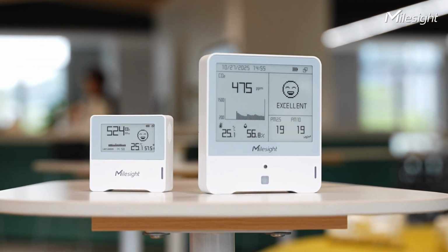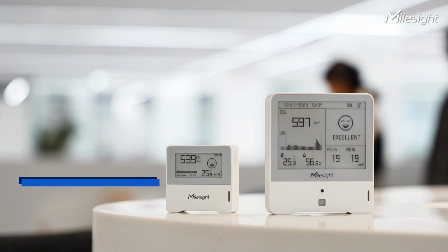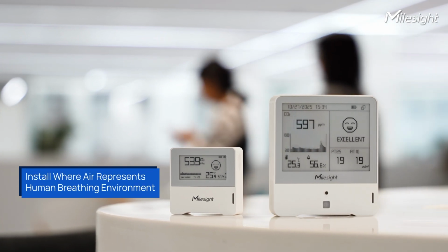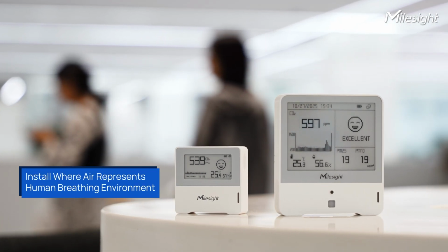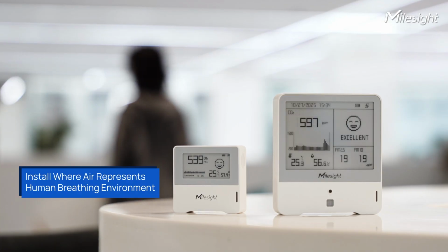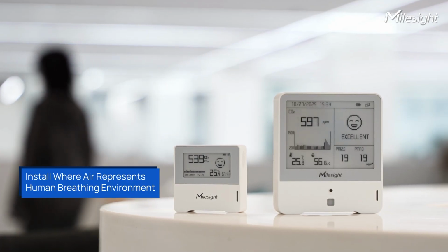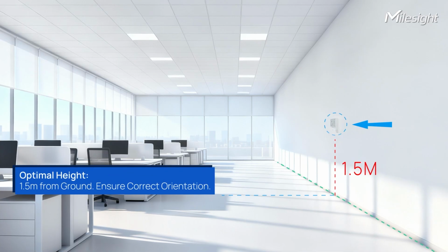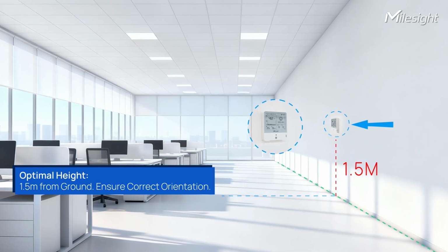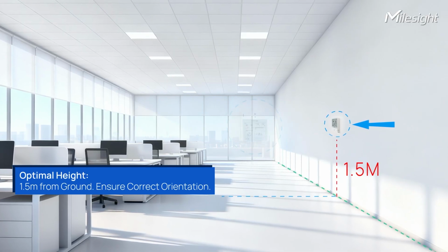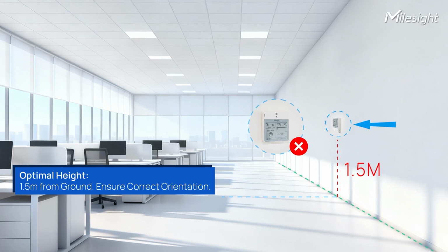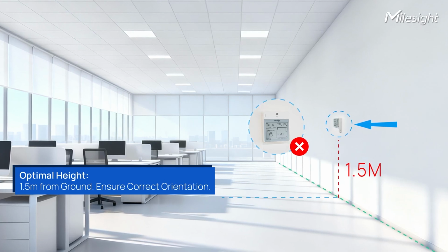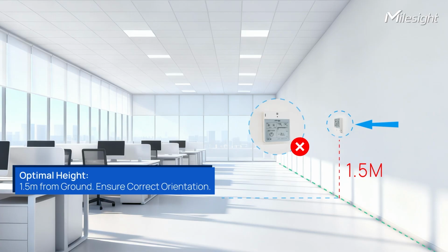Before we start the equipment installation operation, choosing the correct installation location and environment is crucial. IAQ sensors should be installed at a location that represents the actual human breathing environment. The optimal installation height is usually around 1.5 meters from the ground. Remember not to install the device upside down. Ensure the device's orientation is correct to avoid affecting readings.